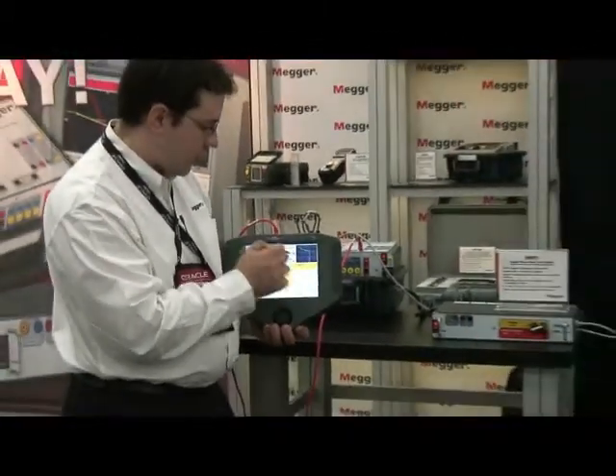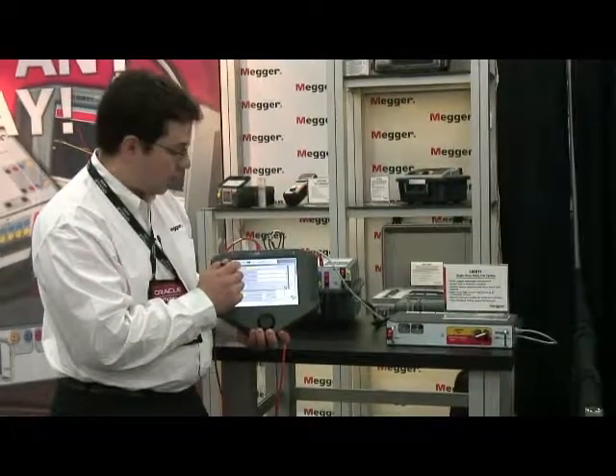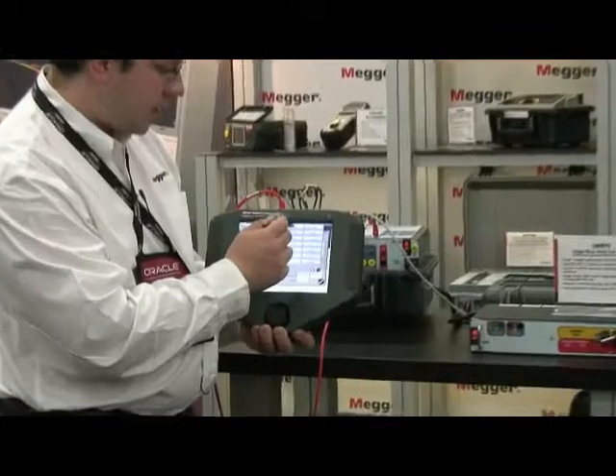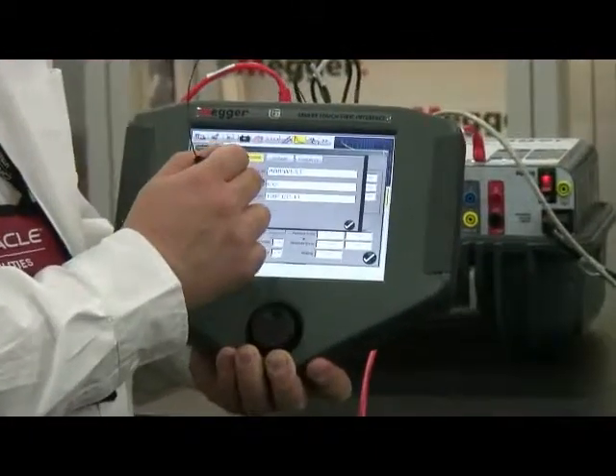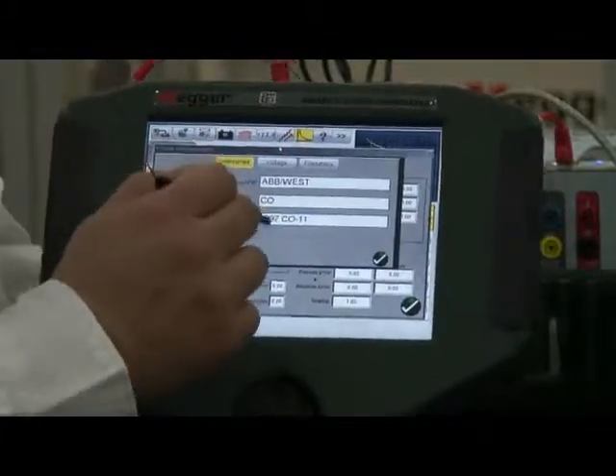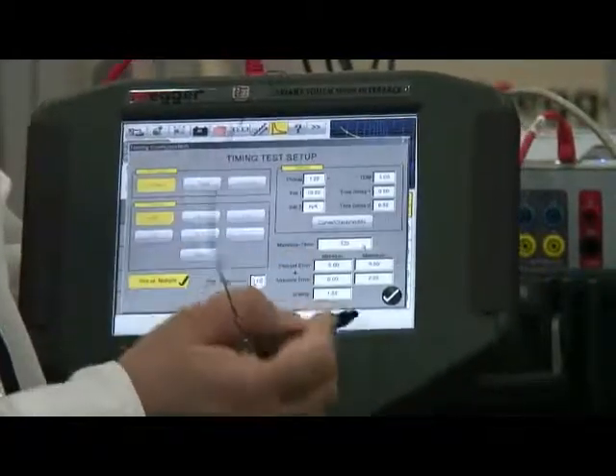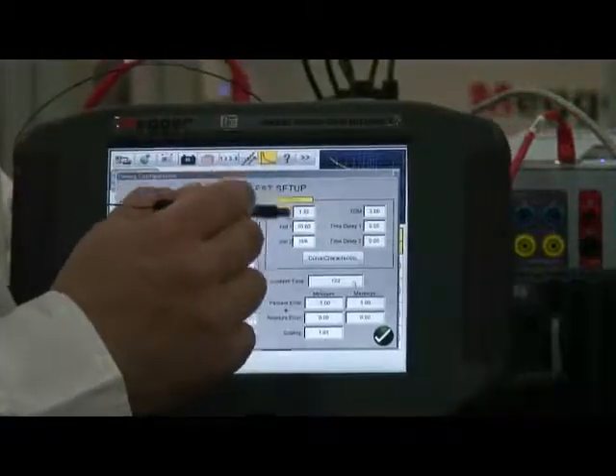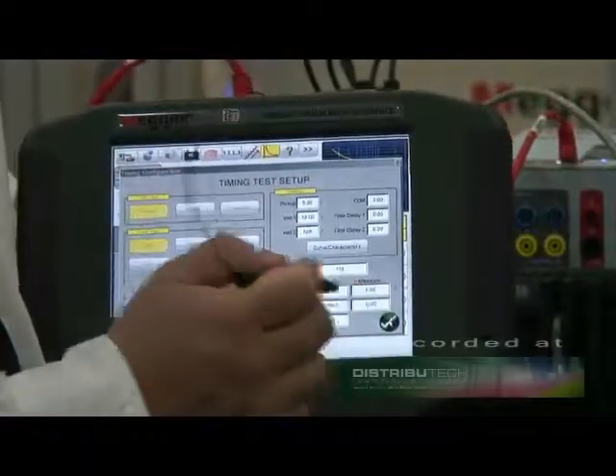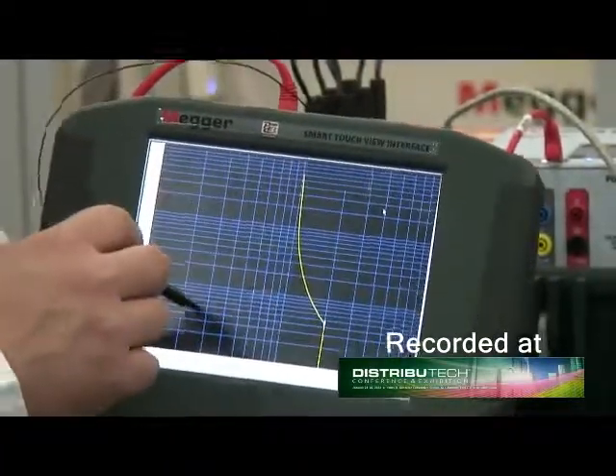In the time over current screen, I can select the type of time over current curve that I need. There are already hundreds of curves built into the STVI. If I want to select a Westinghouse curve, I select Westinghouse and the relay model. I can select the CO relay — say I wanted to test a CO9. I hit OK, set pickup to a 5-amp pickup, and leave the time dial at 3. And voila, here we have a CO9 curve with time dial 3.